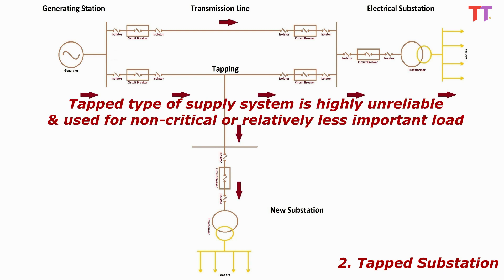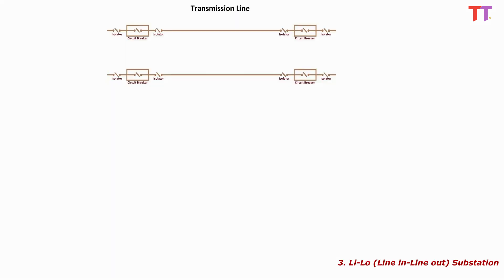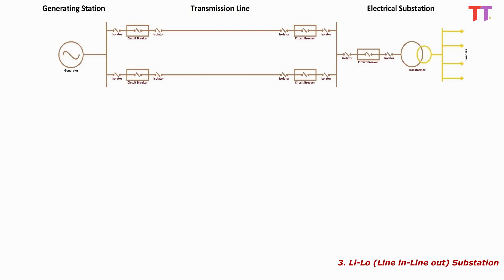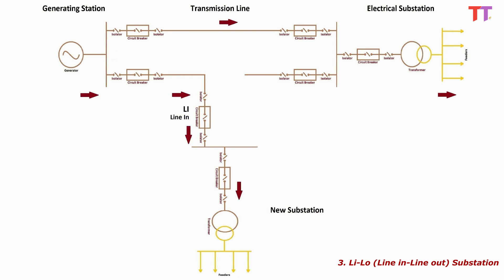Hence such a system is highly unreliable and used for non-critical or relatively less important load. 3. LILO means line in, line out substation. In this type of layout, as the name says, a line is brought in and taken out of the substation. Consider an existing power transmission line connecting two substations, transmitting power in this direction. A new substation is constructed nearby the transmission line. A transmission line is then constructed and taken in as a power source for the new substation, and similarly a line is taken out to feed the old substation, completing the circuit.